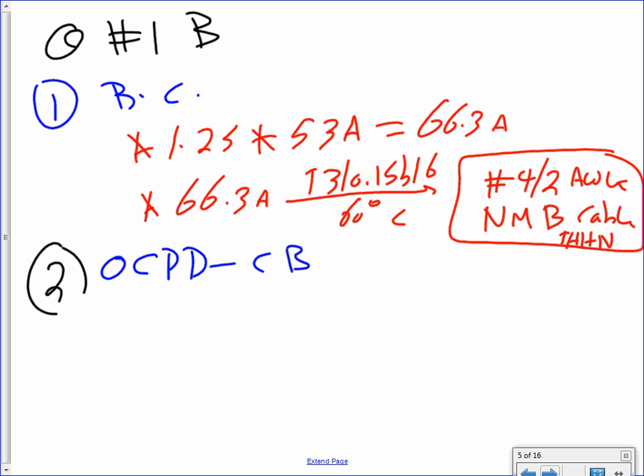Am I making sense, guys, when I say a cable? Here's the three conductors that you have, 2 hots and 1 ground. So these two guys will be wrapped with insulation called THHN. Typically, the ground will be bare. You put them together and you cable them with a cover over them. But they are individually THHN conductors.